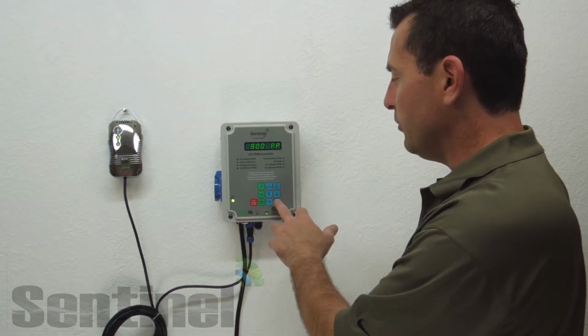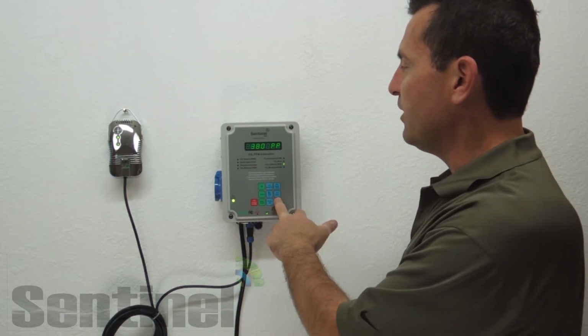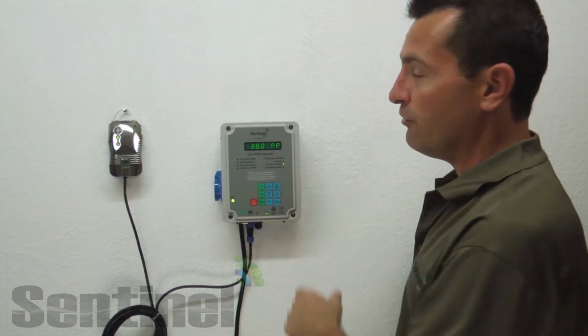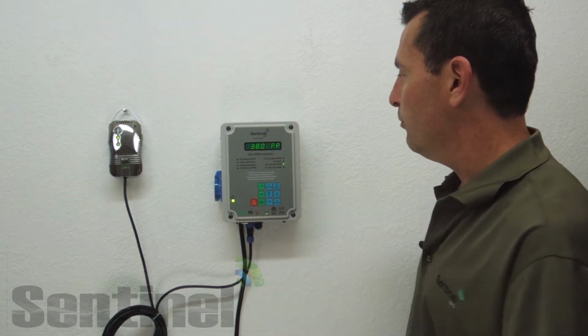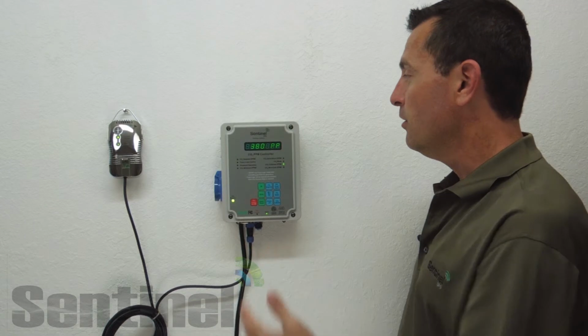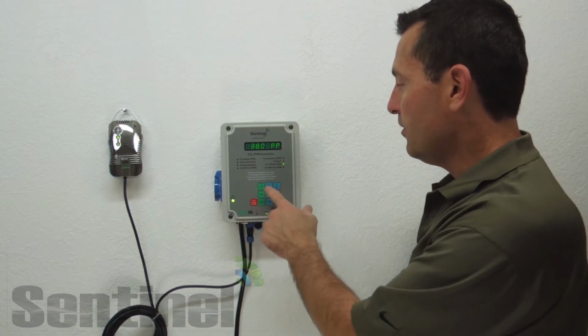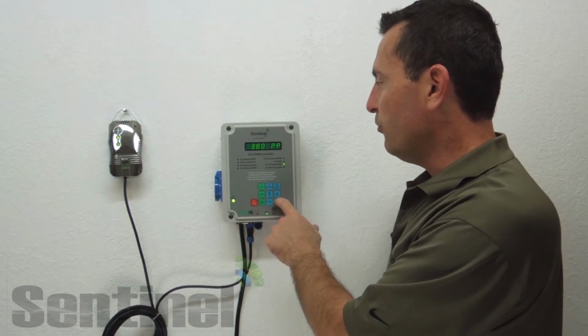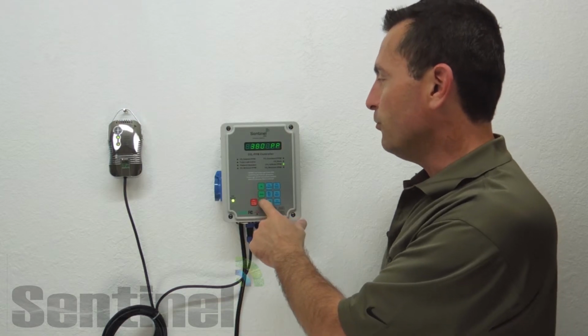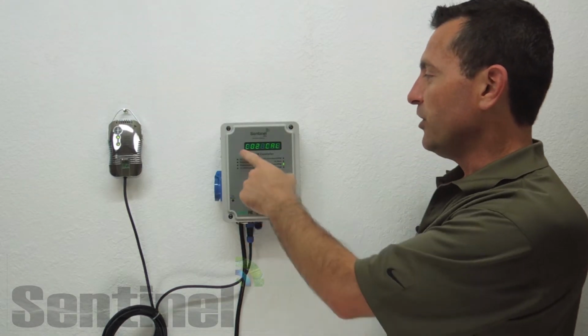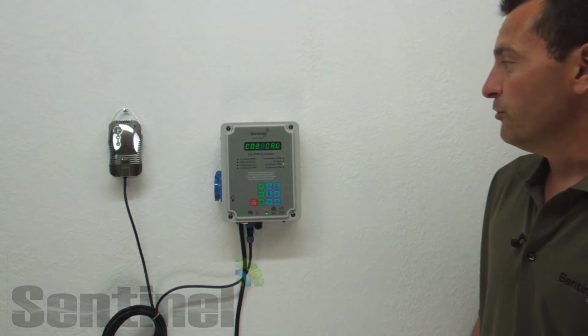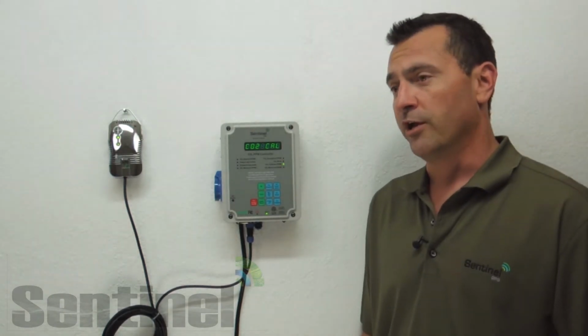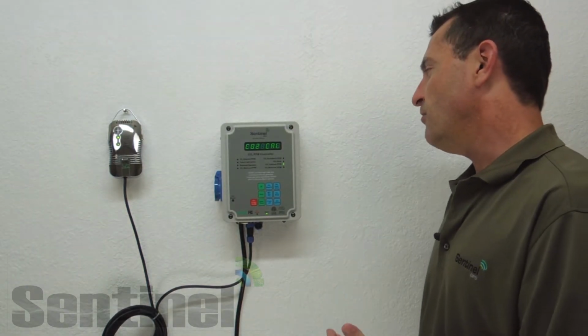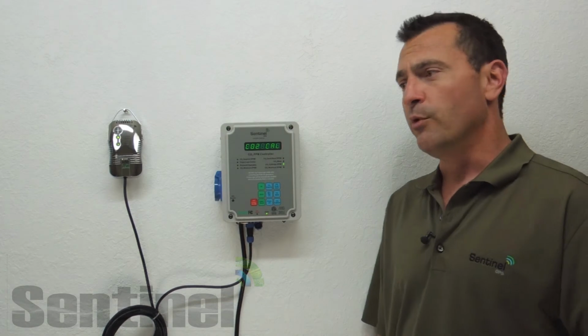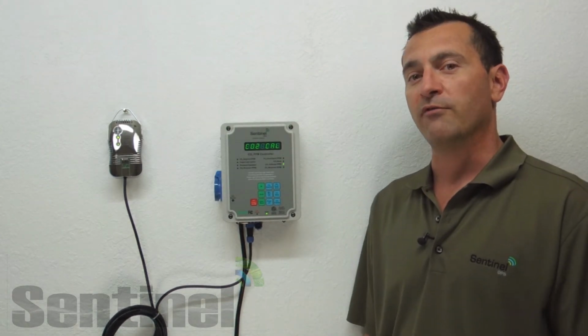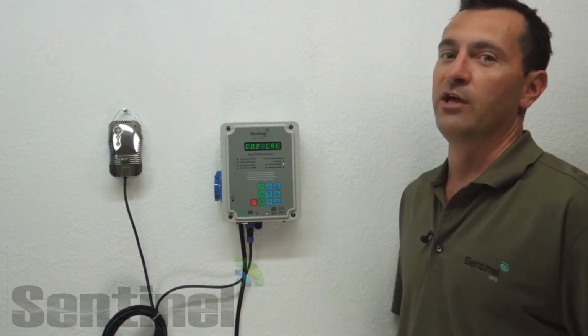Then you come up to your main unit and press and hold the CO2 calibrate button. You'll notice this goes to 380 parts per million, which is what we use as a baseline calibration and what we can refer to as an ambient level. You can then press and hold the enter reset button for about 4 seconds. The CO2 cal feature comes up on the display, meaning it's calibrating. This is going to take about 8 to 10 minutes to calibrate, but we recommend you let it run for another hour after that once again to allow everything to stabilize.